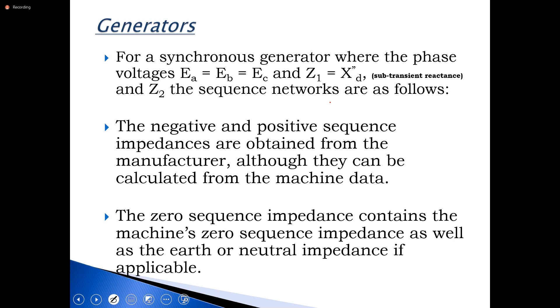So there may be, for whatever reason, the need to just earth the generator solidly, meaning you don't have a resistance in the earth path. All right. If you are doing that, then fine, the zero sequence will just be the machine zero sequence. But if I earth it through an impedance, from a protection standpoint, we can talk about the reason for earthing it through an impedance. All right. I think you'll test it in one of your labs. But for now, just take that, we will have use for it at some point in time. But you'll note it in one of your labs. All right. So in terms of representation, this is how we represent a generator. For the positive sequence network, we have a voltage EA in series with Z1.